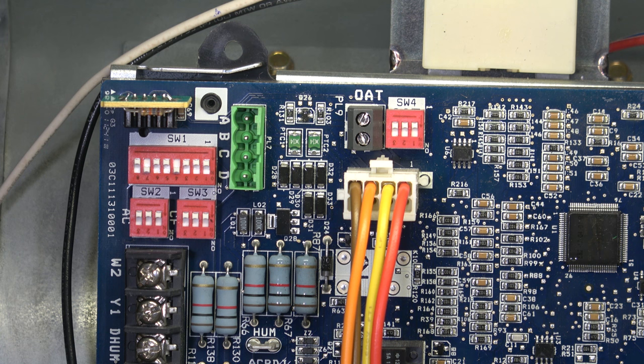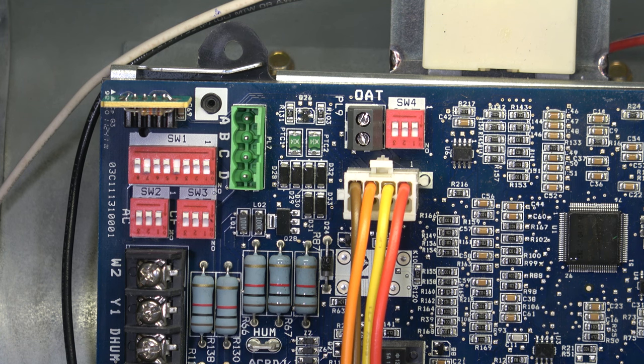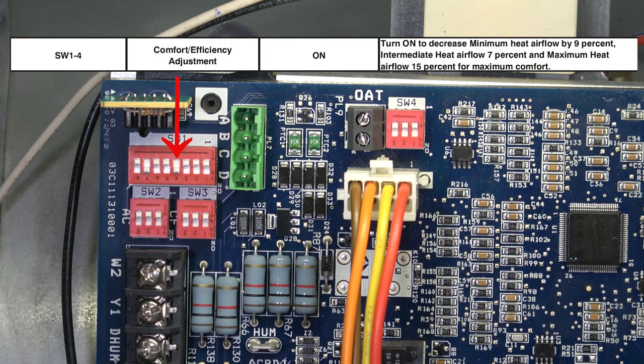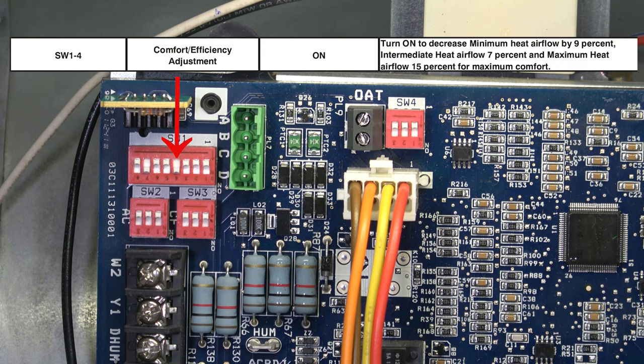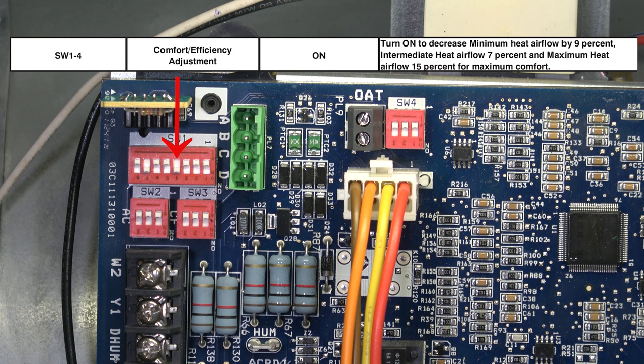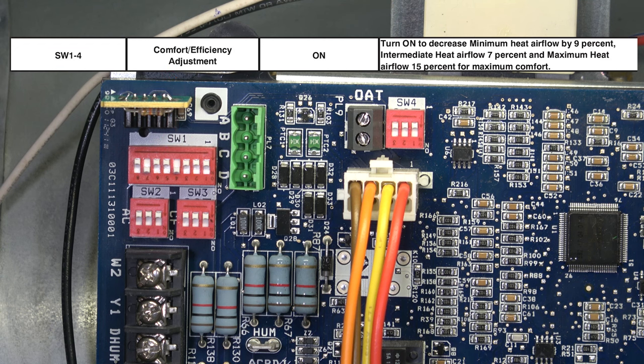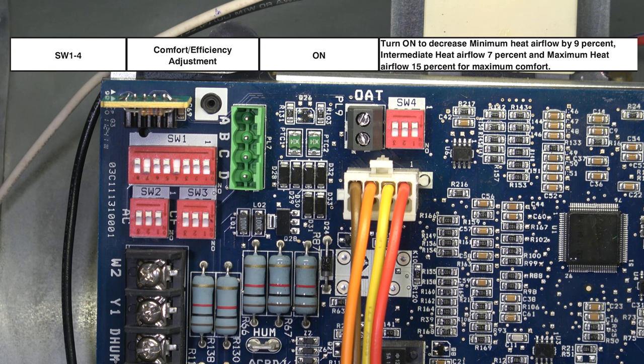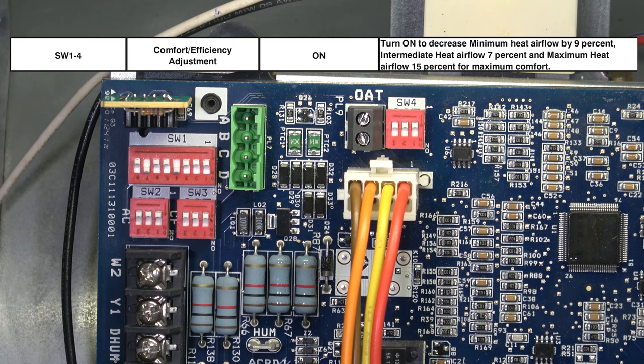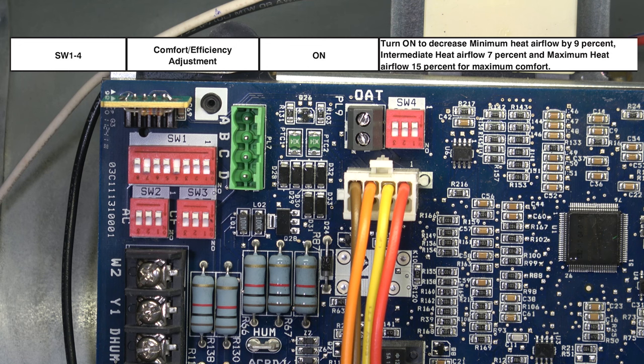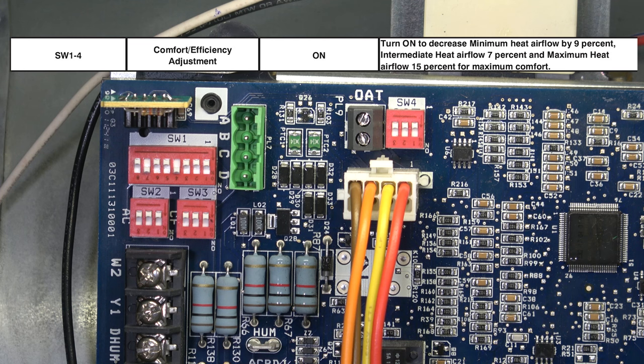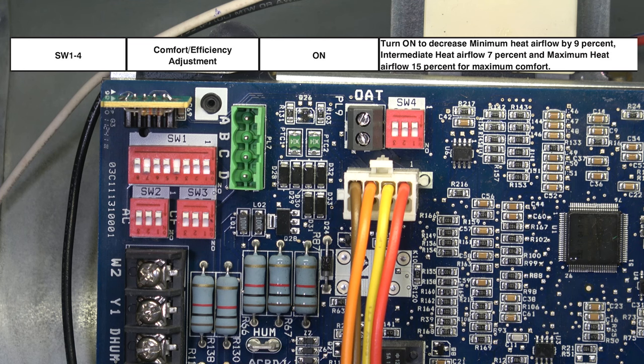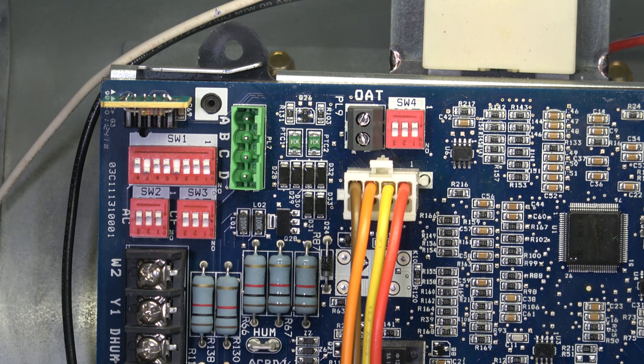Moving to the left, switch one number four is the comfort efficiency adjustment. Normal position is on. When the switch is in the on position, it decreases the low heat airflow by approximately nine percent. When the switch is turned off, it will increase the airflow. So comfort efficiency adjustment on decreases airflow, off increases airflow.